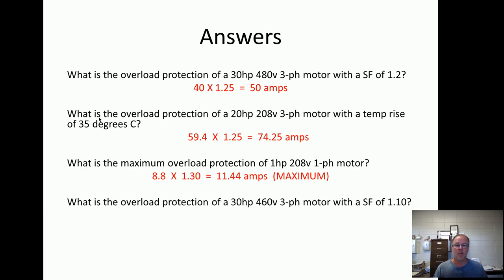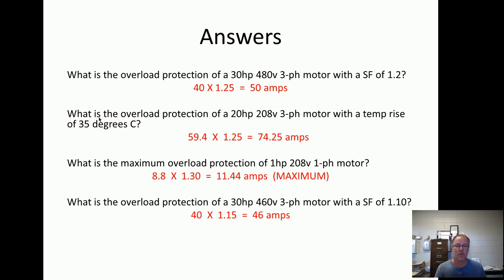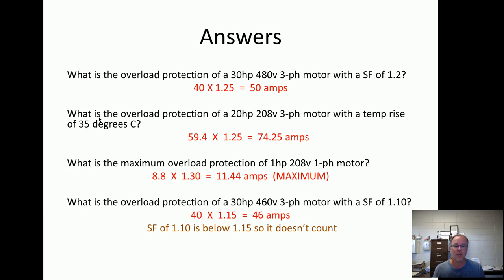What's the maximum overload protection? We use the maximum chart — the answer is 11.44. And this one asks for overload protection on a 30-horsepower, 460 three-phase motor with a service factor of 1.10. It says 46 amps — but wait, 1.10 is below 1.15. The service factor was mentioned but is below 1.15, so it doesn't count. It must be 1.15 or greater before we apply the 1.25 multiplier. So that's a trap.